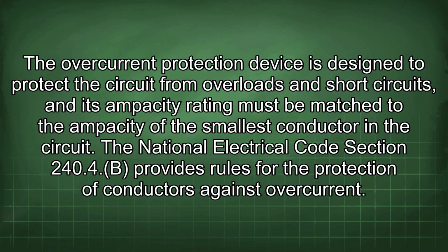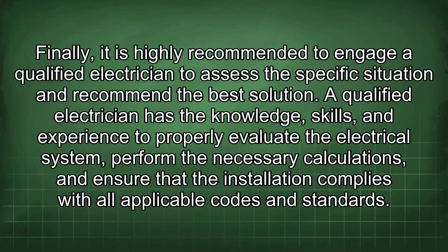The overcurrent protection device is designed to protect the circuit from overloads and short circuits, and its ampacity rating must be matched to the ampacity of the smallest conductor in the circuit. The National Electrical Code Section 240.4(B) provides rules for the protection of conductors against overcurrent. Finally, it is highly recommended to engage a qualified electrician to assess the specific situation and recommend the best solution.